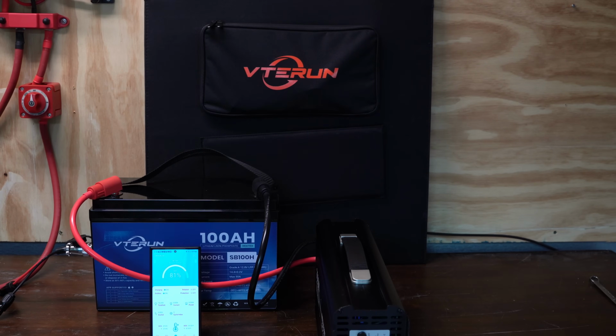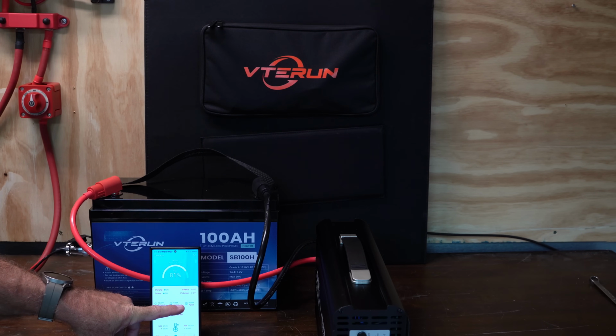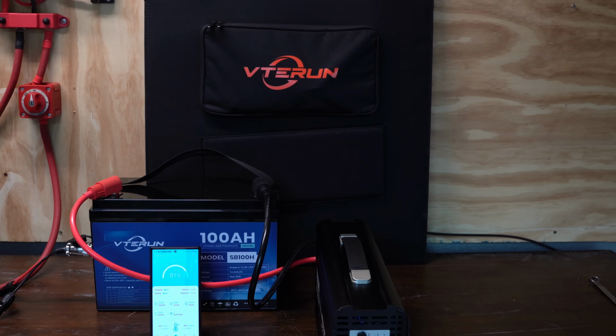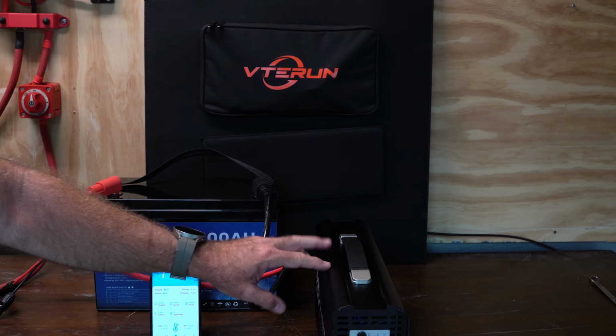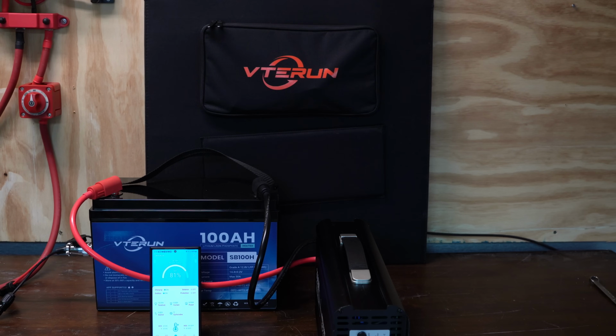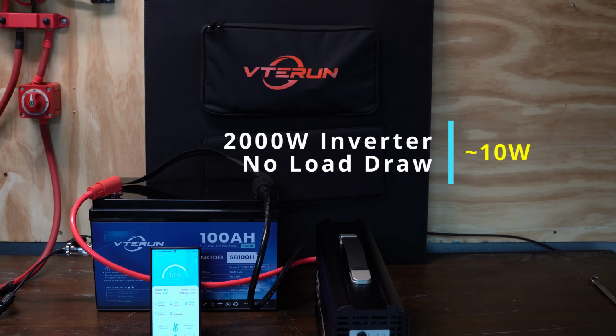It's been almost exactly 4 hours, and interestingly, the state of charge has not budged. I'm currently reading 0 watts out and 0 amps out, so no current draw. According to the manual on this 2000 watt AC inverter, the no load draw should be about 0.8 amps, which equates to just over 10 watts.